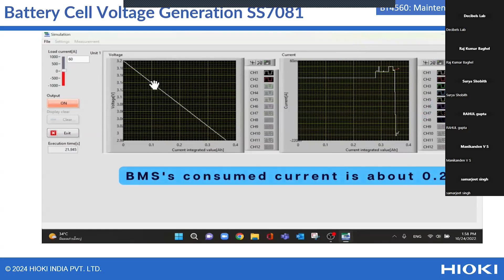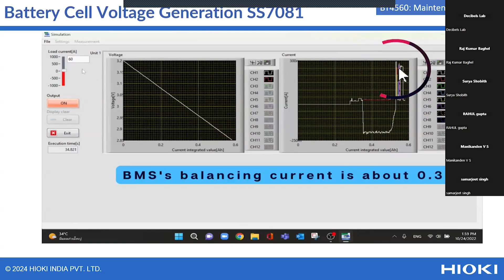Now first you can see here the BMS consumed current. It shows the BMS consumes about 0.2 amps here. And this represents the balancing current of a BMS. So by changing this load current, you can check and test your BMS.